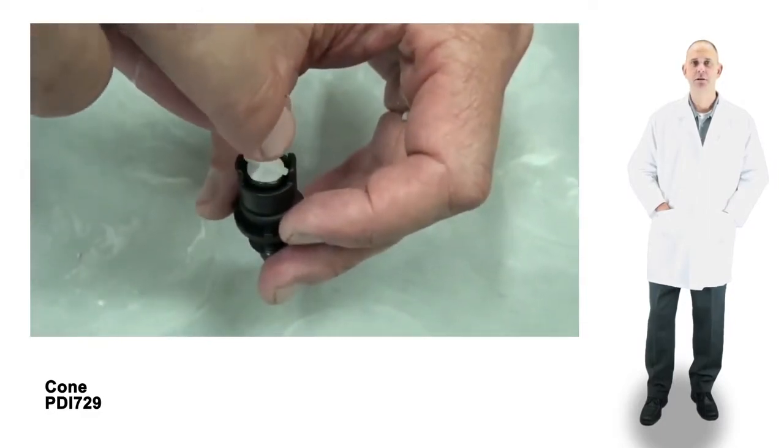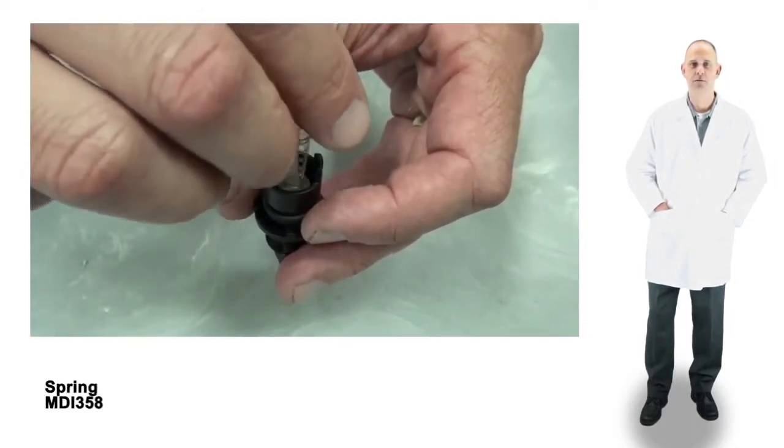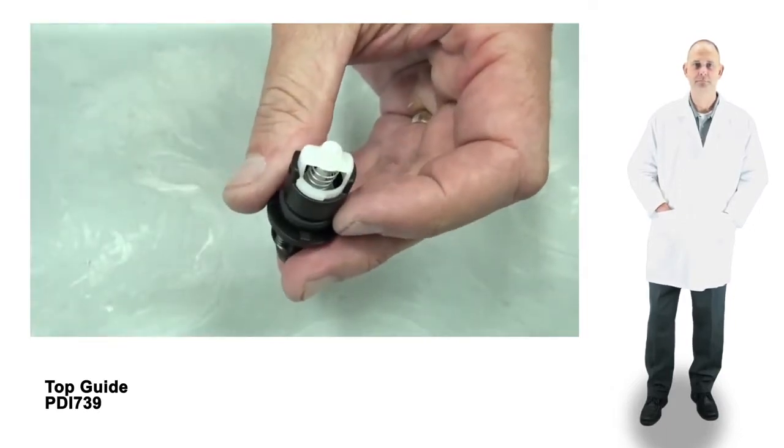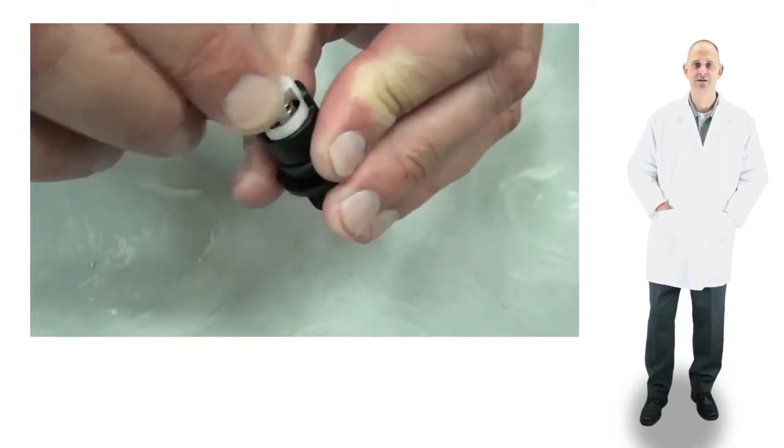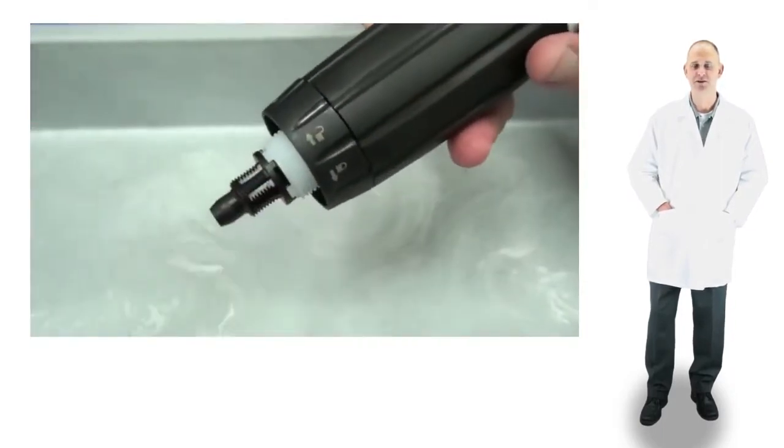To reassemble, put the cone into the top of the barb. Next, slide the spring over the shaft and position the top guide over the shaft. Align the guide and twist it a quarter turn clockwise to lock. Give it a tug to make sure everything is in position. Reinstall the check valve assembly into the stem. Then, reinstall the check valve nut.